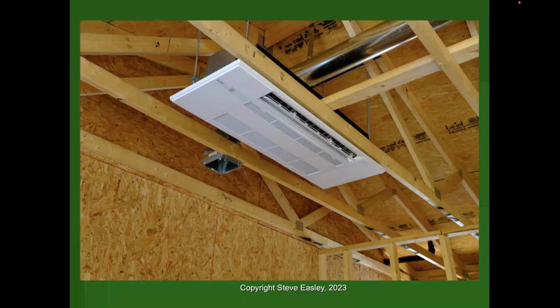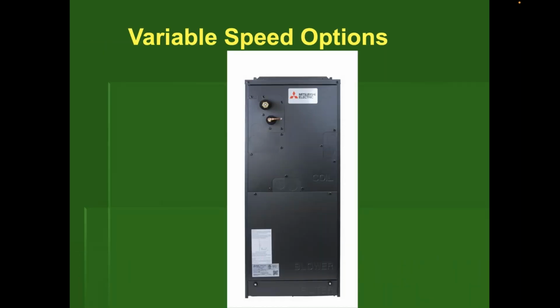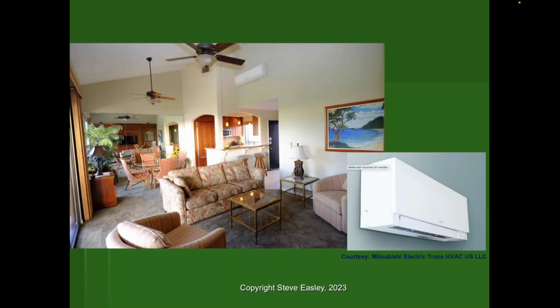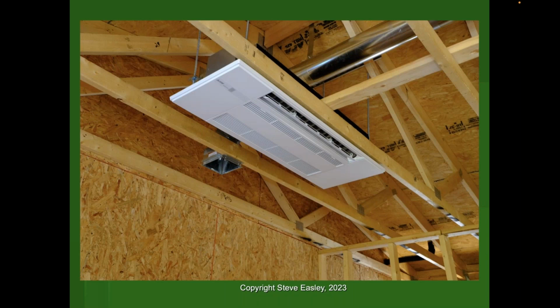Now we go to the house I'm building in Arizona. In each of the rooms, I'm putting in one of these ceiling cassettes. And these, again, are ductless systems. This is ductless, this is ductless, this is ducted. So we can use these inverter-driven heat pumps as a ducted system, or like your traditional mini split system, or like these ceiling cassettes. This is what we call a one-way ceiling cassette. And you might be saying, well, Steve, it looks like it's ducted here. I see a duct. Now, this is where my ERV will bring fresh air into the home. It will dump it in here. This will pull it into the return air side of this coil and will heat or cool it.